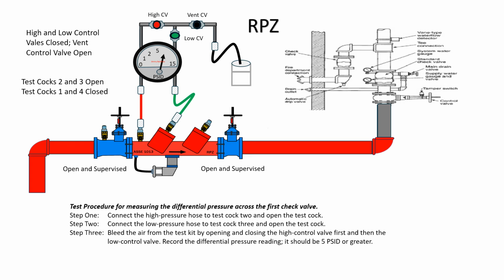Test procedure for measuring the differential pressure across the first check valve. RPZ. Step 1. Connect the high-pressure hose to test cock 2 and open the test cock. Step 2. Connect the low-pressure hose to test cock 3 and open the test cock. Step 3. Bleed the air from the test kit by opening and closing the high control valve first and then the low control valve. Record the differential pressure reading. It should be 5 psid or greater.